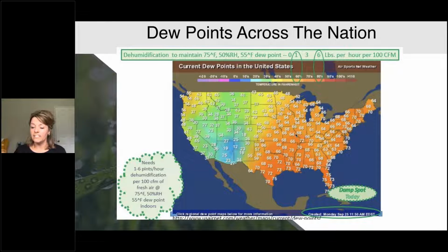So an ideal dew point in our house is a 55-degree dew point. If we're not running air conditioning at this time, we're going to have to figure out other ways to dehumidify our homes. If we were bringing in 100 CFM of fresh outdoor air for our ventilation rate, depending on where you are on this map, you're going to need about 1 to 6 pints an hour of dehumidification in order to control the moisture in your home.